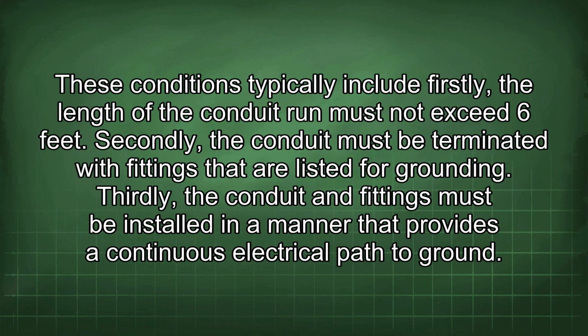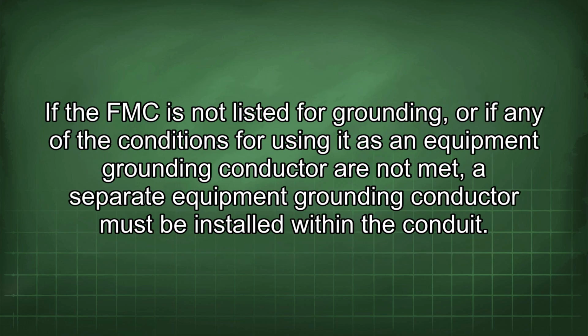These conditions typically include: firstly, the length of the conduit run must not exceed 6 feet. Secondly, the conduit must be terminated with fittings that are listed for grounding. Thirdly, the conduit and fittings must be installed in a manner that provides a continuous electrical path to ground. If the FMC is not listed for grounding, or if any of the conditions for using it as an equipment grounding conductor are not met, a separate equipment grounding conductor must be installed within the conduit.